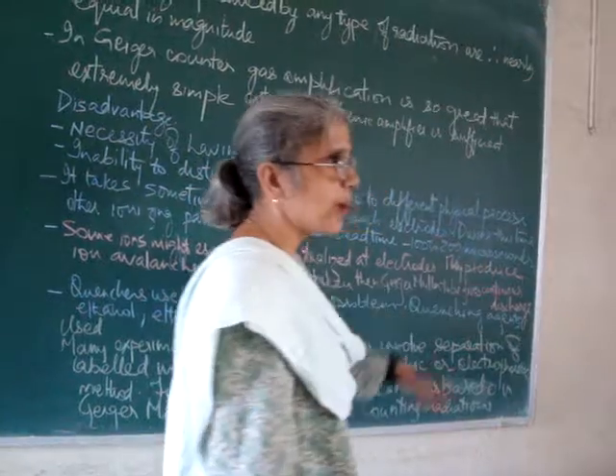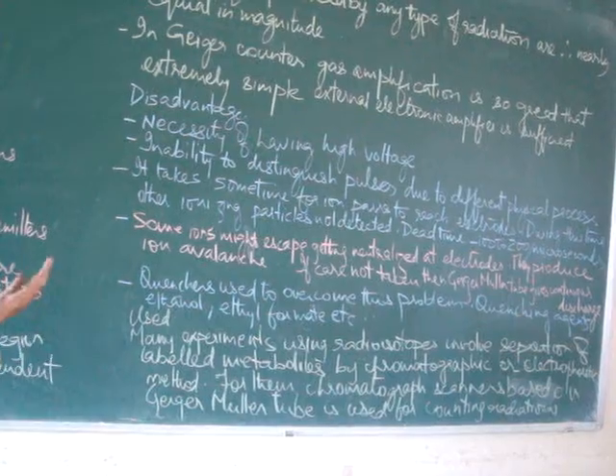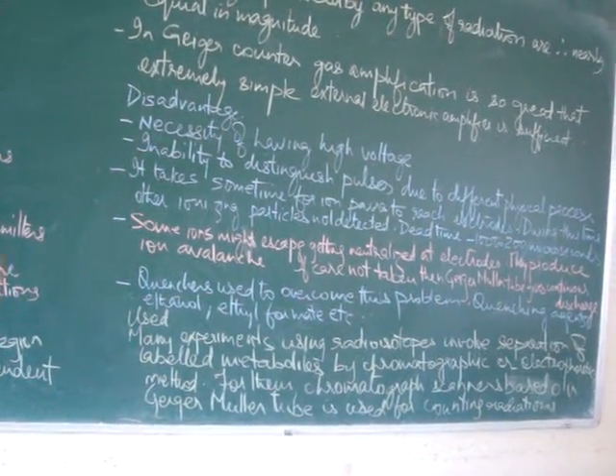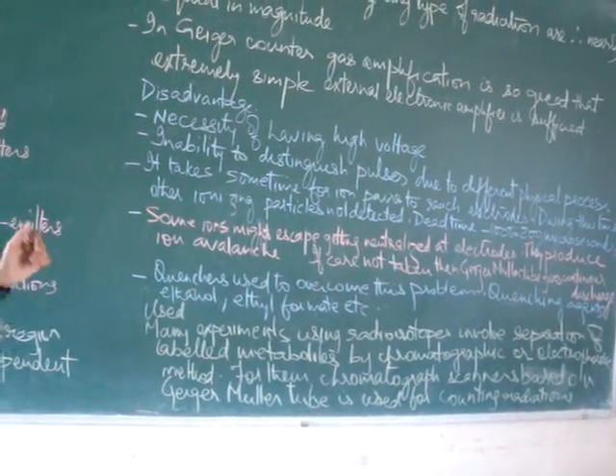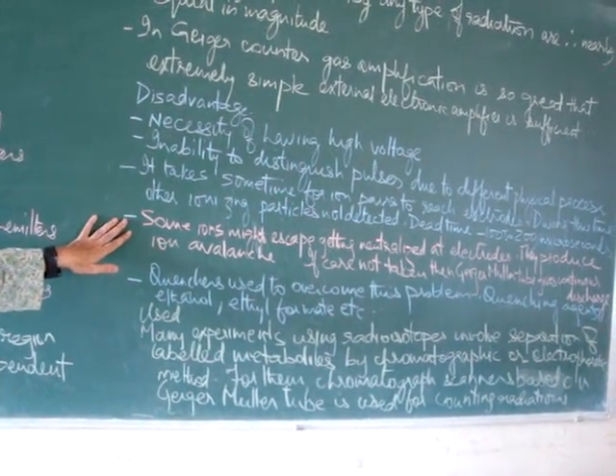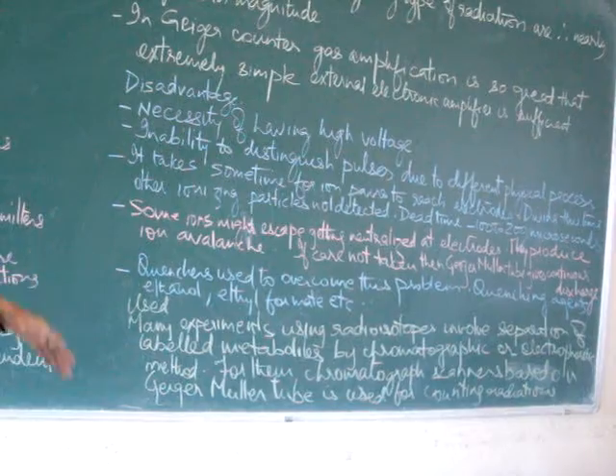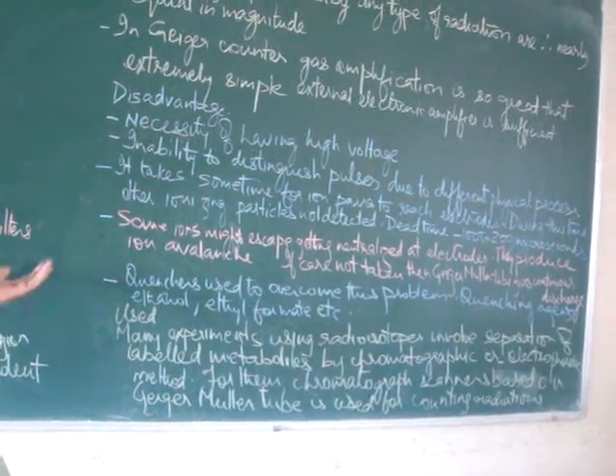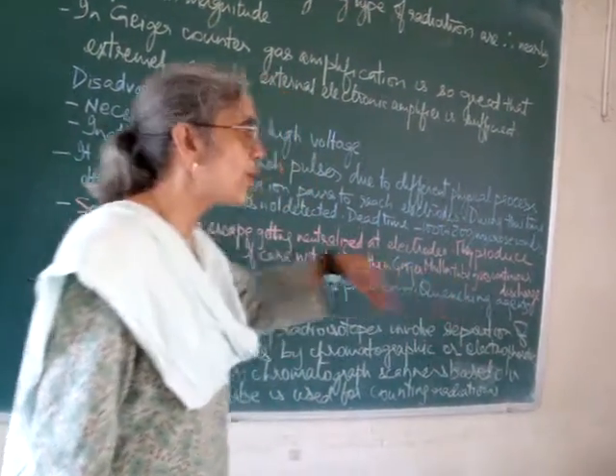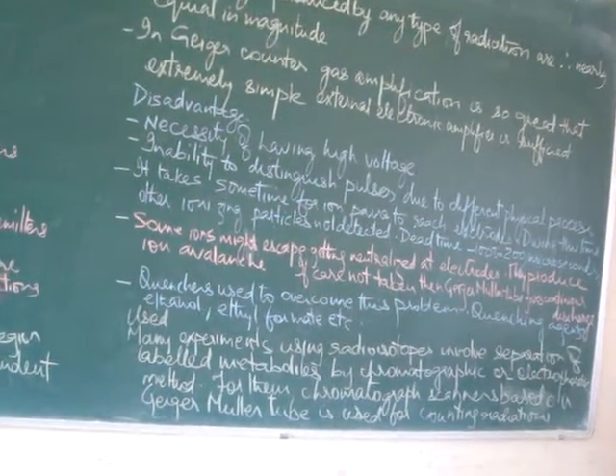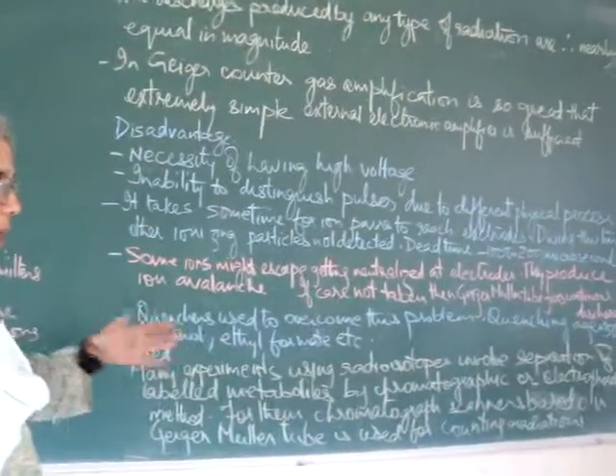This dead time is about 100 to 200 microseconds in case of Geiger counters which is too big, and some radioactive events may not be counted. Some ions might escape getting neutralized at the electrodes, recombine and produce an ion avalanche. If care is not taken the Geiger counter tube will go into continuous discharge and the instrument will get spoiled. To prevent this, quenchers are used.